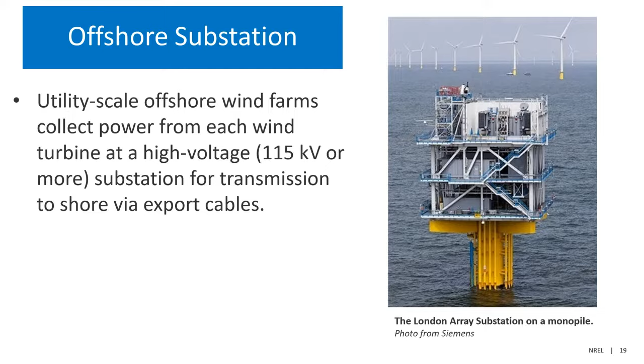A small project like Block Island isn't going to be competitive in the energy markets because it's too small. When you get up to the Vineyard Wind scale, 800 megawatts, now we're talking about cost-effective projects that can be put in place and compete in the energy markets—but you need substations to do that. These are connected at high voltage to the land-based grid, with high voltage being a minimum of 115 kilovolts, though it can be more. These export cables carry power from the substation to the land-based substations, and all of the turbines on their array strings are connected to this.